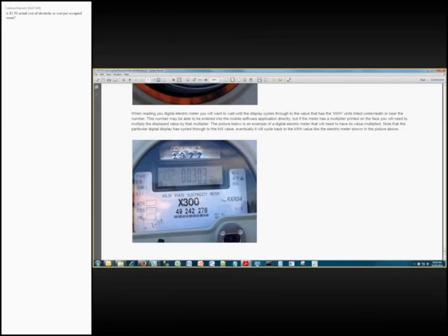So we have a meter multiplier of 300. For instance, when this screen rotated and brought up the kilowatt hours value, say in this case it's 100, you would multiply that 100 by this 300 to get the value we enter into the system. So if it was 100, or let's make it easy, let's make it 10. Make this math really, really simple.